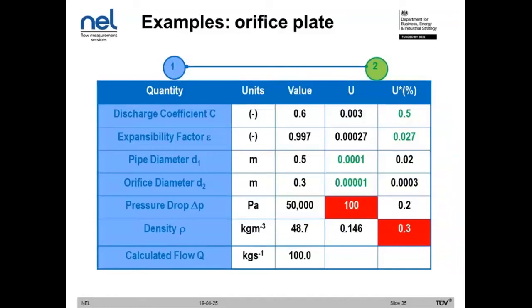But for something like discharge coefficient, we can get that from the ISO standard for differential pressure devices. Assuming that the orifice plate is manufactured to the correct tolerances and it conforms to the standards, in this case ISO 5167, then we can get an estimate of the uncertainty for the discharge coefficient from that standard. So we're fairly confident that we have an accurate value of the uncertainty of the discharge coefficient. In this table, all of the values that are in green are the uncertainty sources that we're very confident in, which have been determined in this case from a standard. This is the same for expansibility factor. Pipe diameter and orifice diameter are based on the manufacturing tolerances of the device, which again should be in conformance with the standard. So we're very confident in those.